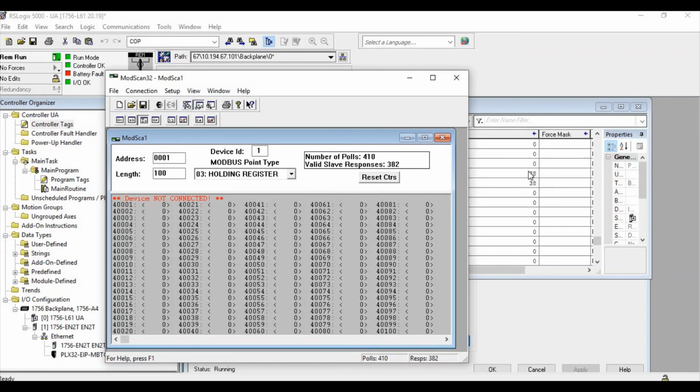If the value stops increasing for some seconds, depending on how fast you poll your Modbus data, then you can trigger the disconnection warning. If I connect back, you can see that the value keeps increasing. This is how we monitor Modbus TCP/IP client and server status on an EtherNet/IP PLC.